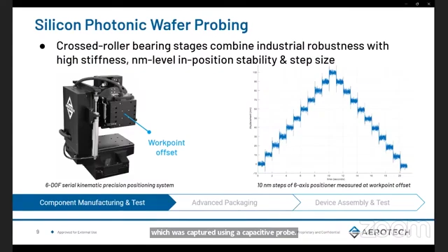This system utilizes non-contact motors and high life cycle cross-roller bearings to ensure industrial robustness and high stiffness, while also minimizing 3D geometric errors, capable of achieving 10 nanometer steps at the work point offset as shown in the plot, which was captured using a capacitive probe. This system's single-digit nanometer level in-position stability and minimum incremental motion are highly suitable for wafer probing applications.